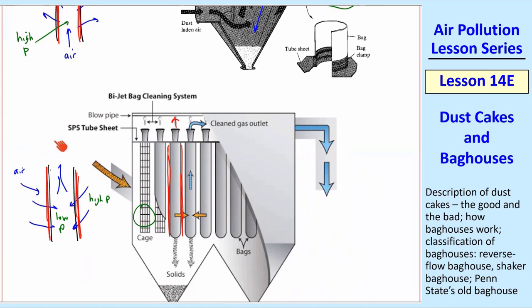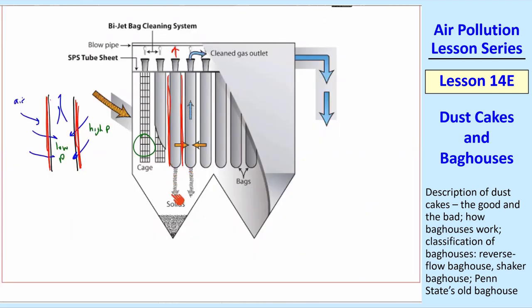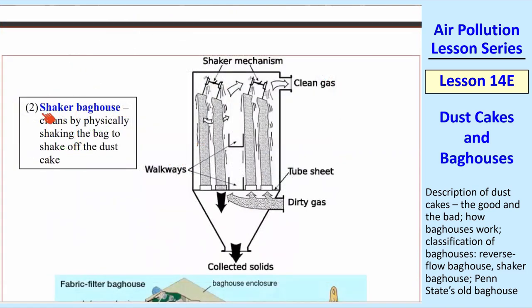To clean these bags, we blow the air the opposite way — the air is blown into the bag, pushing the bag out and stretching it away from the cage. That's what dislodges the dust cake. Once you dislodge the dust cake, the particles just fall down into a hopper. The second kind is called a shaker bag house, where you remove the dust cake by physically shaking the bag. There's some mechanism that shakes the bag and the dust cake just falls off into the hopper.